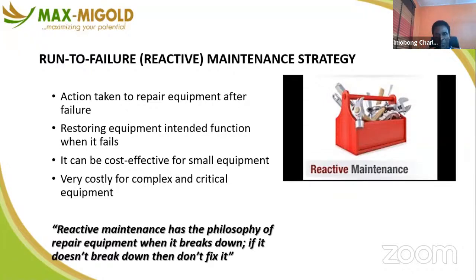If it doesn't break down, then don't fix it. That's the idea. If you look at your facility today, about 90% of the assets fall under this run-to-failure maintenance strategy. The main ones that can go under preventive maintenance might be the generator, the AC, and a few others. But the rest, about 90%, fall under run-to-failure. That's why when an FM brings me a plan showing 60% of assets under run-to-failure, or 50% under preventive maintenance, I know immediately there's an error in that plan, and it cannot fly when you take it to management for approval.